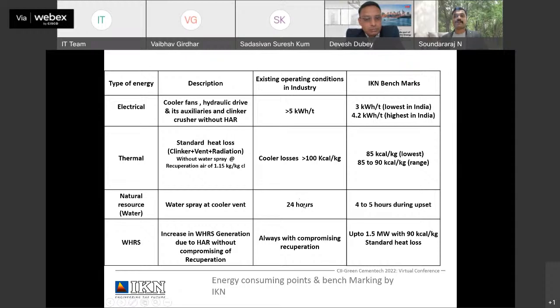our lowest number in India operating at 3 units and highest number operating at 4.2. So there is an average difference of 1.5 to 2 units compared to the existing operating conditions in the other coolers in the industry. Whereas thermal energy also, similarly, we have 15 kilocalorie difference, and in the natural resources of water, we are using only 4 to 5 hours in a day, only during upset conditions.